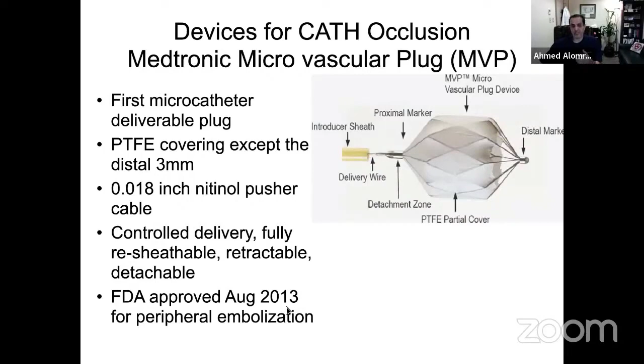It comes in many sizes, but mainly the one used for the neonatal PDA is the MVP 5Q, whose target vessel diameter is between 3 and 5 millimeters, which is the commonest size that we're going to face in these preemie PDAs. One important factor you have to understand is the unconstrained device length. It's up to 12 millimeters.